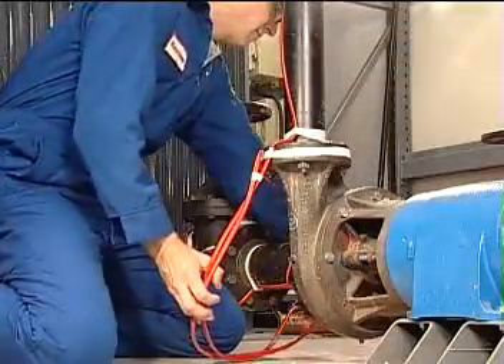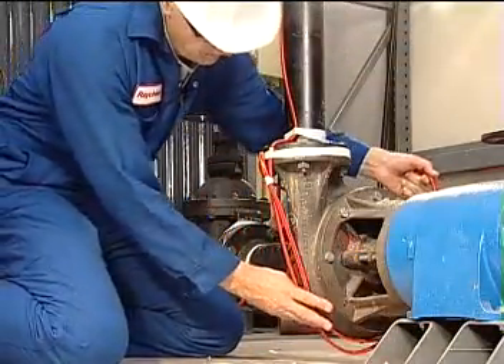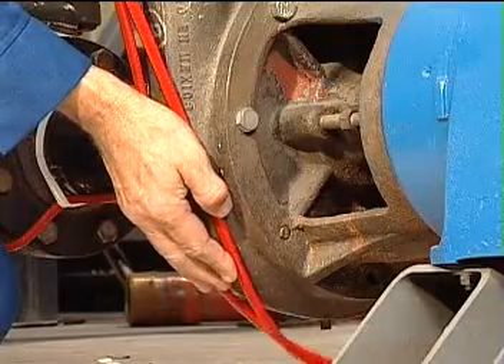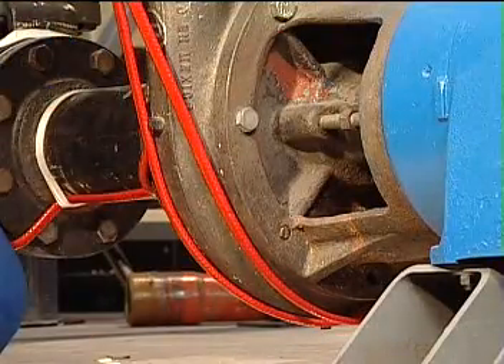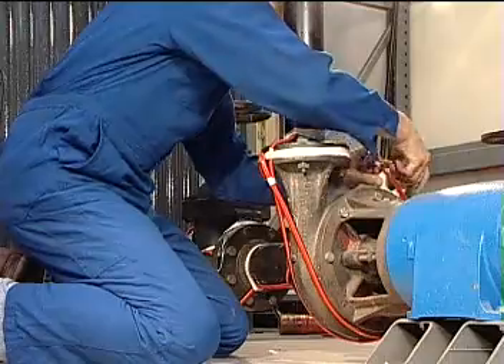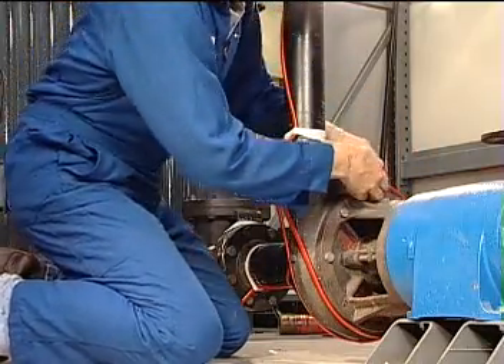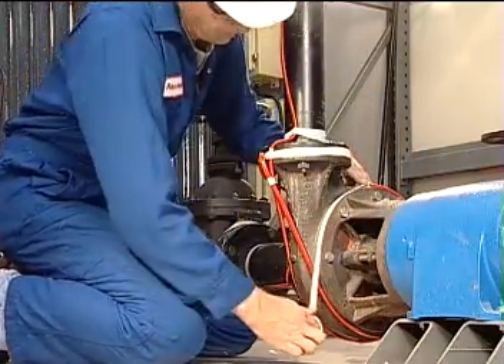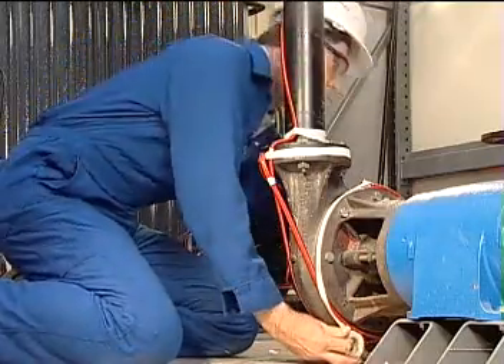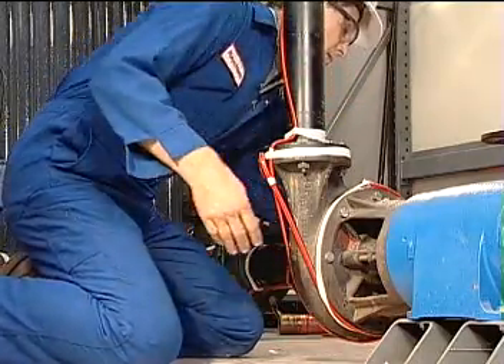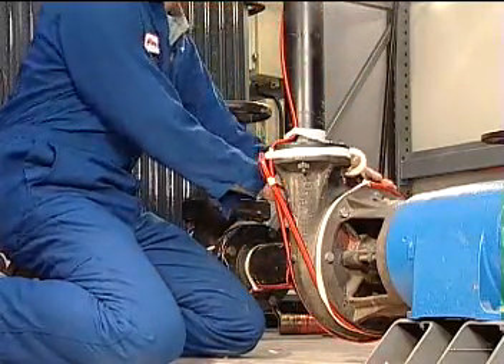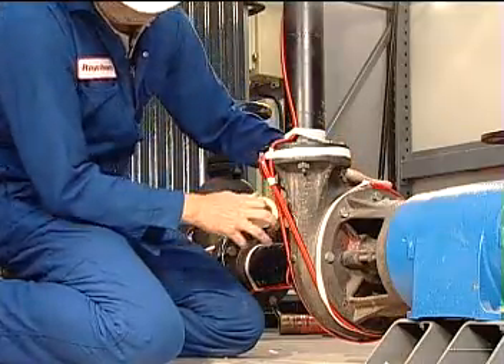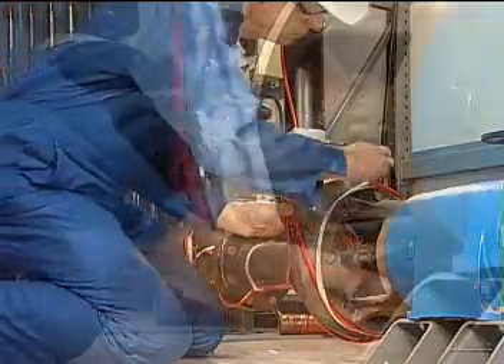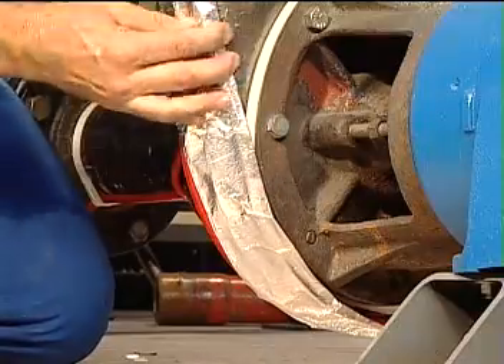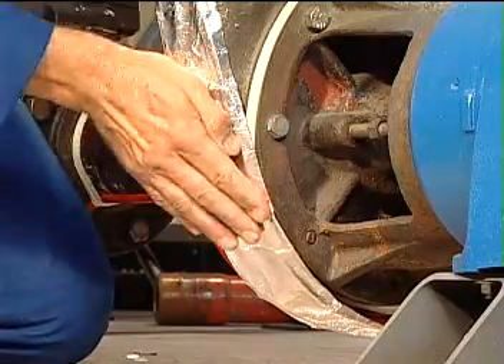The pipes leading into a pump and the pump body itself should be traced with the heating cable. Do not mount the heating cable on the motor or coupling. The motor and coupling have no fluid in them and are not insulated. Therefore, they do not require heating cable. There is also a danger that the cable could get tangled in the spinning motor coupling. A service loop here will allow a pump to be removed without cutting or damaging the cable. Applying AT180 aluminum tape for attaching the heat trace on the pump can be helpful.